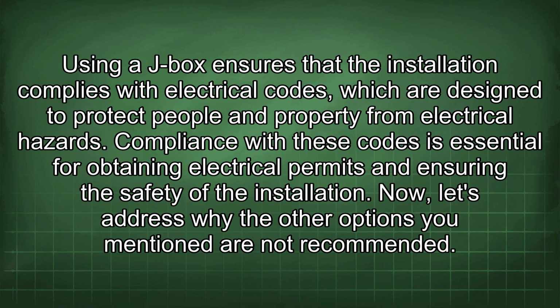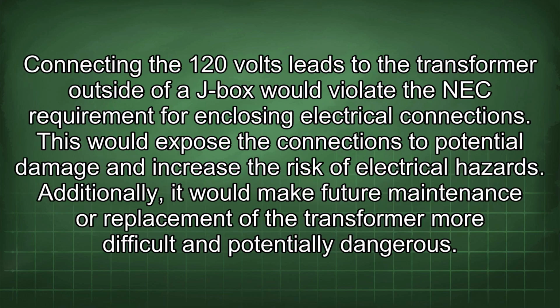Using a J-box ensures that the installation complies with electrical codes, which are designed to protect people and property from electrical hazards. Compliance with these codes is essential for obtaining electrical permits and ensuring the safety of the installation. Now let's address why the other options you mentioned are not recommended. Connecting the 120 volt leads to the transformer outside of a J-box would violate the NEC requirement for enclosing electrical connections.